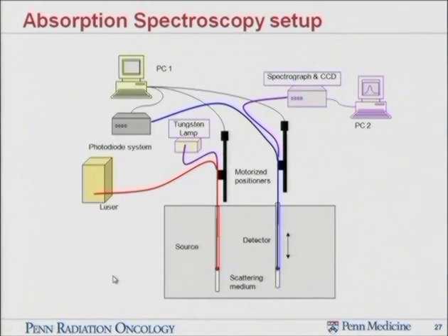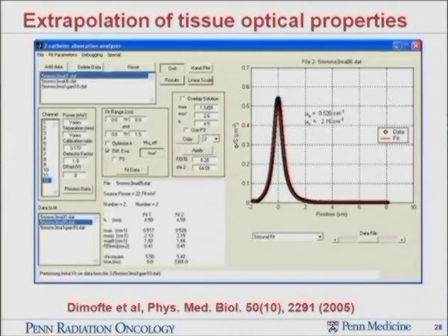And then you move the point source to different locations in the prostate, and do a scan from the point source, and that will be used. So the typical result looks something like this. And a scan is very quick. It takes about 2 seconds.